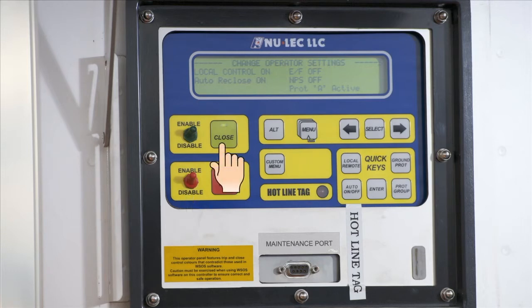Close key generates a close request to the processor when the panel is active. A lamp is embedded in the key to indicate its operation. Another lamp is used to indicate whether this key's operation is disabled. Close disable switch disables all close operations. When the switch is in the disable position, the close circuit in the switchgear is electrically disconnected from the control electronics. Thus, the switch provides a physical isolation point for the control circuitry. The switchgear cannot be closed, an audible alarm in the panel will sound, and the disabled LED in the close key will flash. The close key operates normally when the switch is in the enable position.